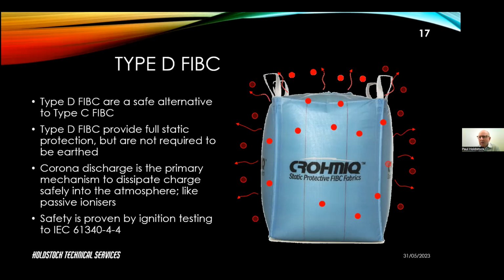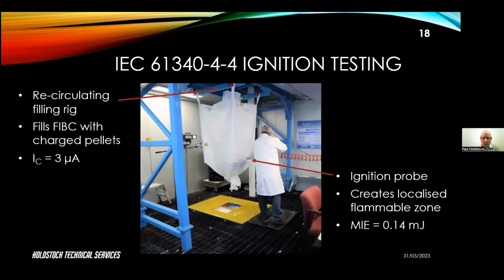Now, there's no simple way of determining or testing these bags like you have with a Type C, where you would measure resistance to earth. But what you have to do is make sure that no incendiary discharges can be produced from the bag, and we do that by ignition testing, and that is described in the IEC standard 6134044. So this is a photograph of the test rig that is compliant with the IEC standard. All the testing is always done on full size FIBC, and it tries to simulate the actual filling and emptying conditions. Most of the tests are done during filling. There are also tests done while the bag is being emptied.